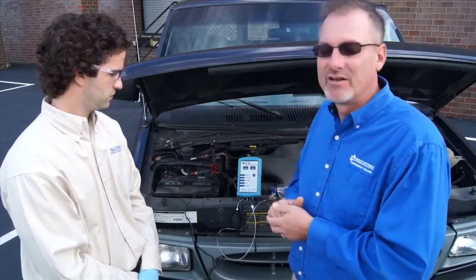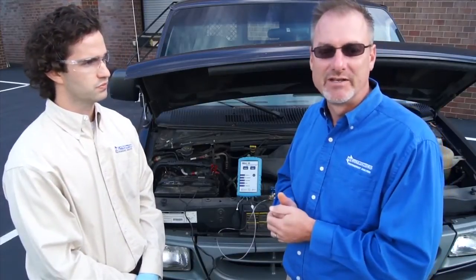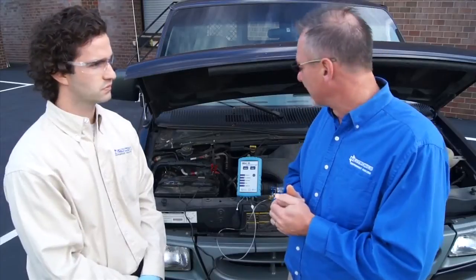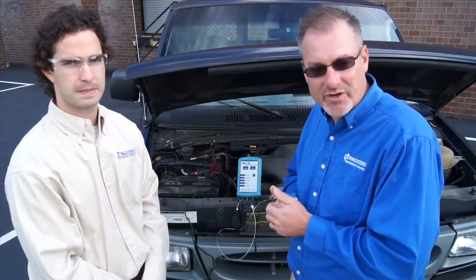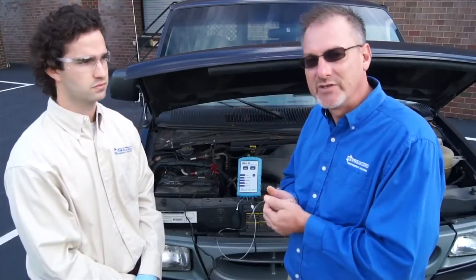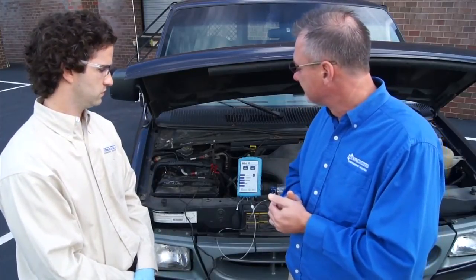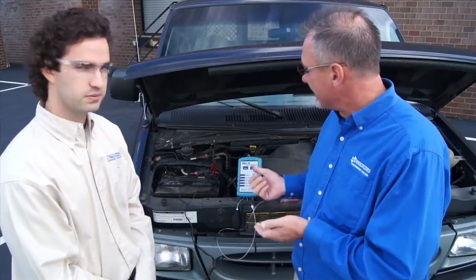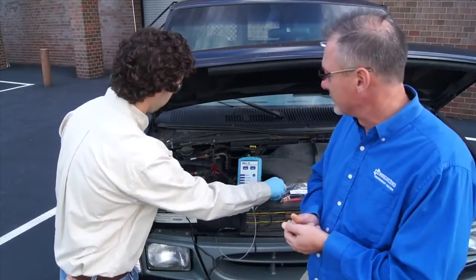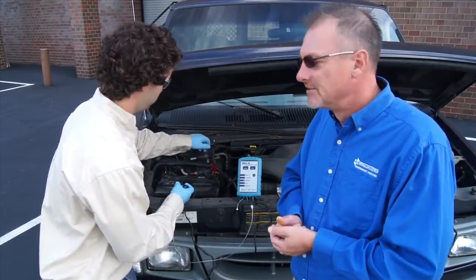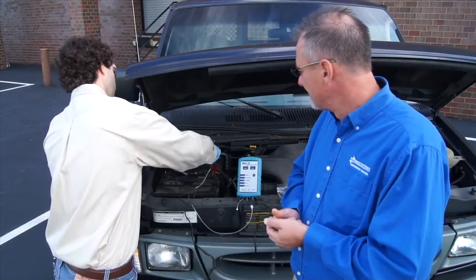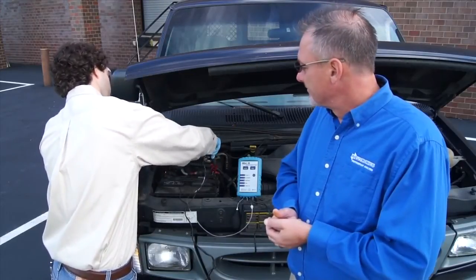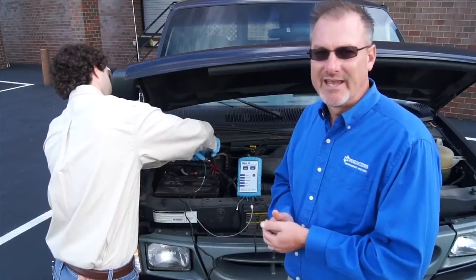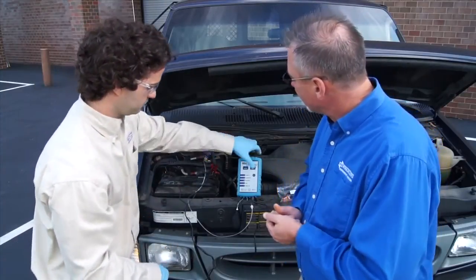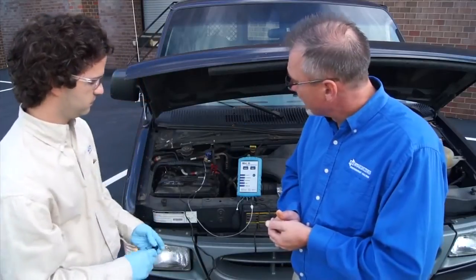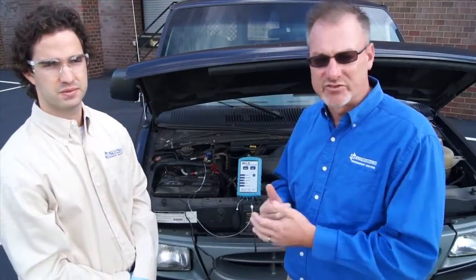Once calibration is done, it'll be a flashing light on the analyzing button, and then we'll go forward and connect the coupler. We don't want to connect the coupler now. We don't want to do that until we're ready to actually do the analysis of the refrigerant. And now we've got the analyzing light, so Zach will go ahead and connect that coupler to the low side service port. Screw down the actuator to engage, and we're ready to go. Push the next button, and now we're testing. Again, we're about 60 seconds or so to test.